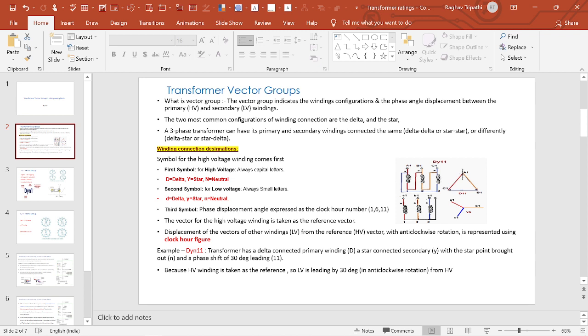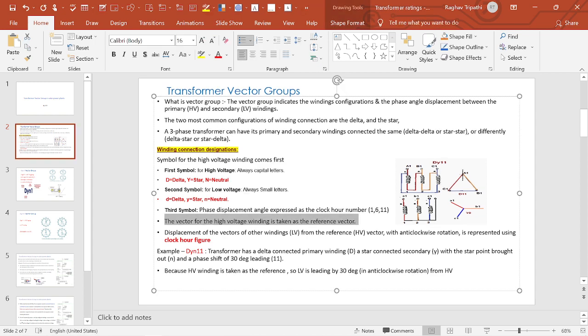The vector of the high voltage winding is taken as the reference vector, and the rotation is taken as anti-clockwise. The displacement of the LV vector from the reference HV vector in anti-clockwise rotation is represented using a clock figure — 1, 6, or 11. For example, DYN11 means HV is delta, LV is star with neutral, and 11 indicates the phase displacement.